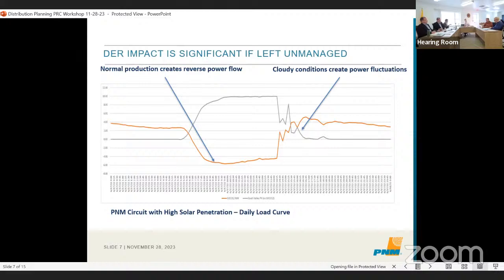This is our duck curve on one of our distribution feeders, and it's becoming more common. This is real data from our system captured at the substation. The gray line is the solar production on the feeder, peaking at almost 10 megawatts. The orange line is the load, or power flow, on that feeder. There are hours in the day with reverse power flow, minus 6 megawatts flowing back onto the system at the substation. That tells us generation is greater than load, turning the distribution into two-way energy flow, with power flowing backwards.